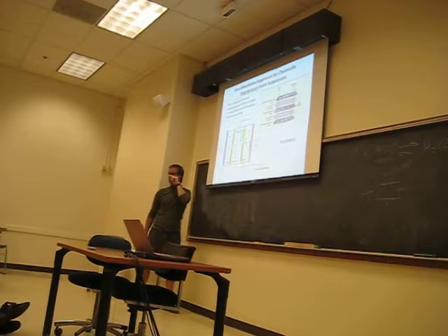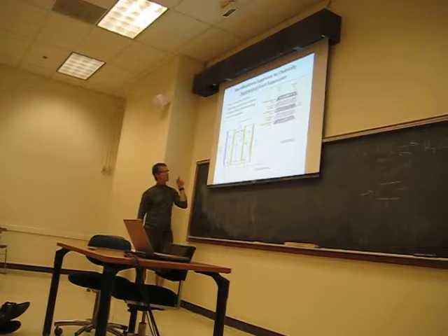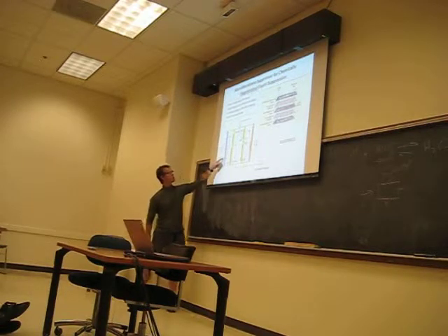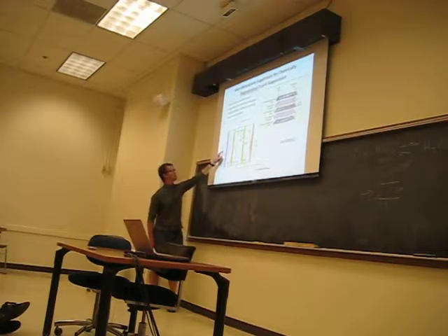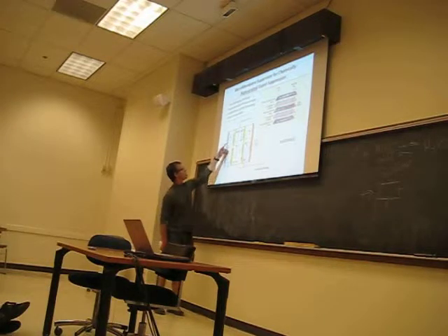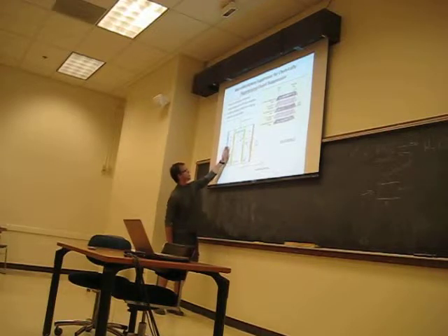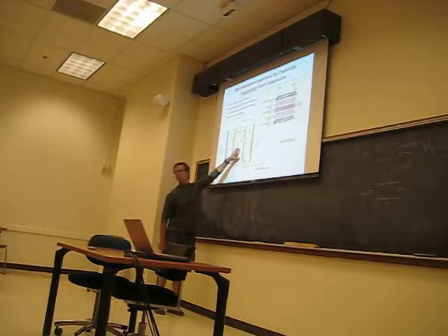And if you look closely at the tube coming out of the suppressor in the instrument, there's a tube that's taking the regenerating solution from the suppressor that's recycling it. And if you look closely at it, you see a lot of air bubbles in there. And those air bubbles are the oxygen that's being formed by the oxidation of water at this anode.